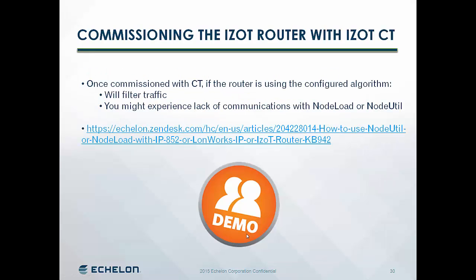So if we want to commission our IzoT router with IzoT CT, normally we would use a configured algorithm, or the router type will be configured. However, this will filter traffic. So by way of a heads up, if you want to use NodeUtil from the Ethernet side or from LonTalk IP, then you would need to change the router's algorithm temporarily to a repeater.